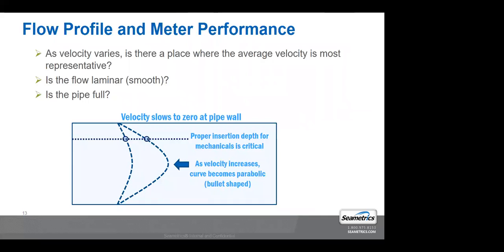The reason it's critical to install the meter with enough upstream and downstream run has to do with the velocity and the swirl going through that line. You want to make sure you're getting a good flow profile going through the line. It is extremely critical on mechanical meters that they are installed with the proper upstream and downstream.